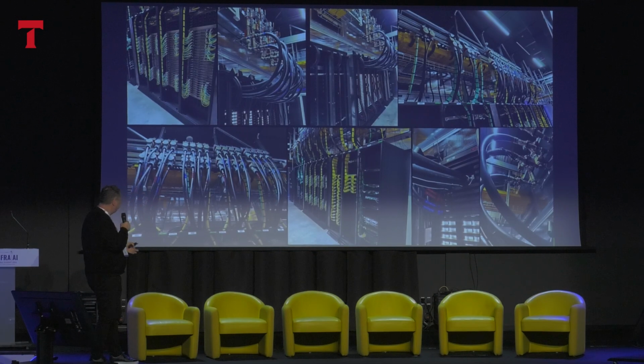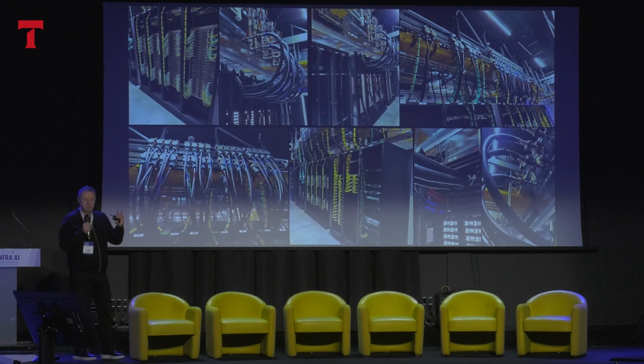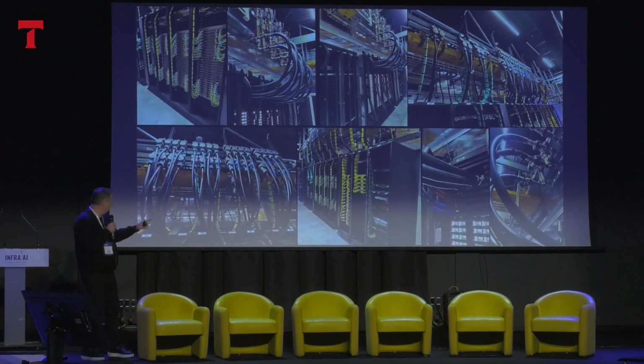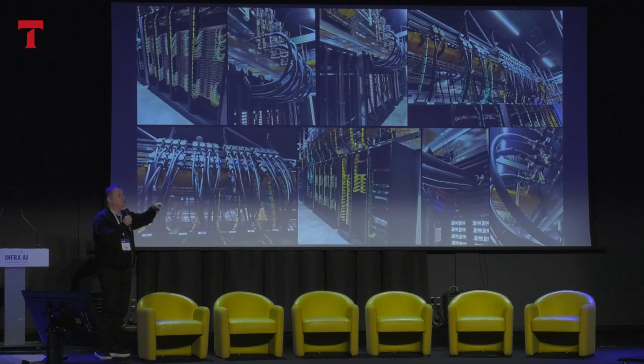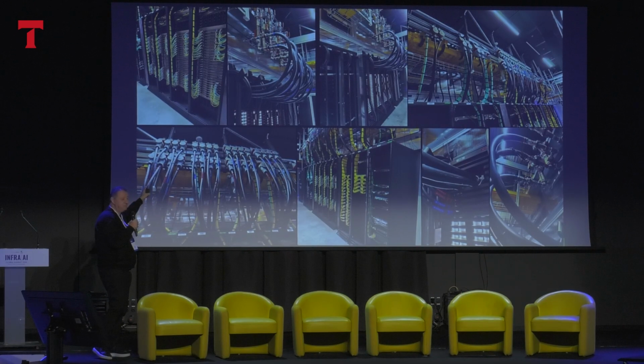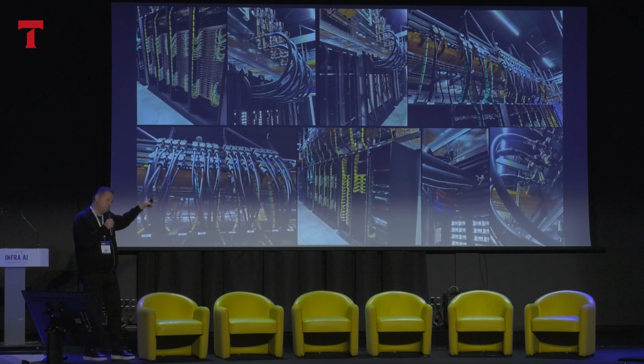What you are seeing is, when you have air-cooled racks, usually it's only 2 power connections. With these racks, because it's 125 kilowatt, you're moving from 16 or 32 amp to 63, and you have 8 power connections. With the new generation of Vera Rubin, which is coming this year, we are moving from 63 to 100, 125 amp, also with 8 connections.